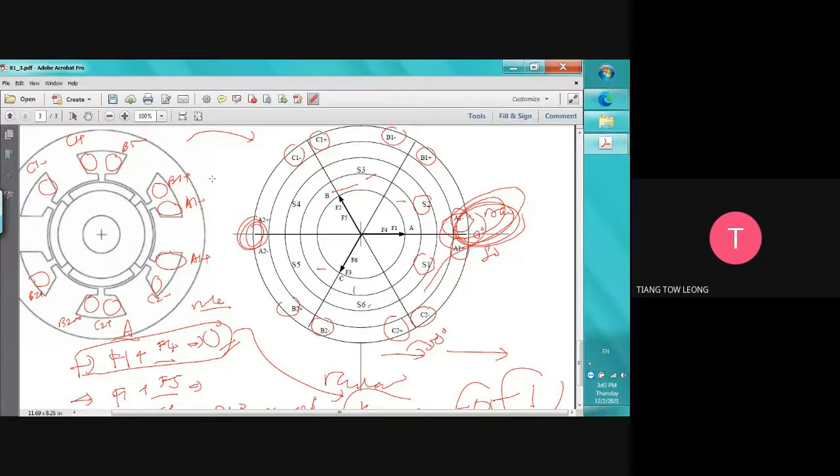So in this winding, for phase A, let's say this one is the starting point. This will go to A1 plus, then this will be A1 minus, then this must be A2 plus, then this will be A2 minus. After we give the coil, the line will jump to here, connect to here, and then coil again, then come out. So for phase A, it only has one enter, one out, like this. This is the so-called winding layout.